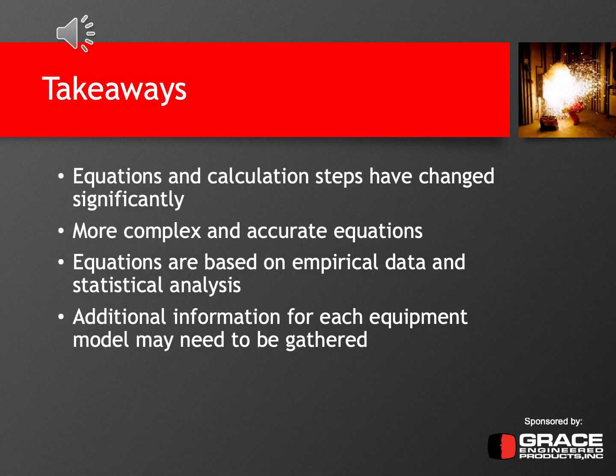So in closing of this presentation, I wanted to go over again the takeaways or the learning points from the very beginning of the presentation. And the overarching one is that the 1584 2018 edition standard has changed significantly from the 2002 edition. While the outcomes and some of the steps are the same, how you go through those steps and how you get those intermediate outcomes have changed significantly. Partly due to the change in the equations, the more accurate and more complex equations based on more available test data and the statistical analysis that was performed on that test data, as well as the need to gather additional information as inputs into the 2018 edition arc flash study, which were not available in the 2002 arc flash study.